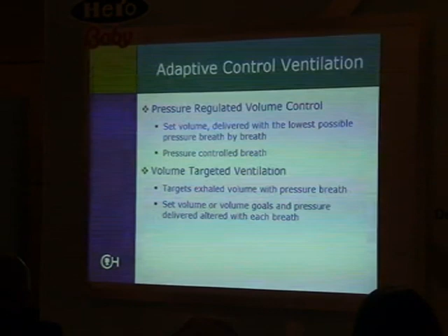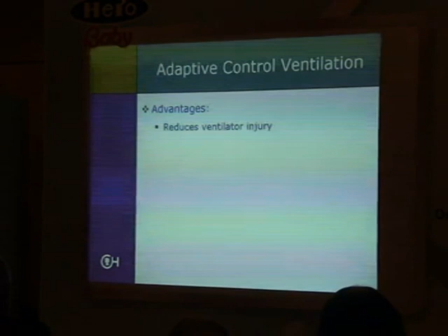Some of the advantages with this, there's the reduced amount of lung injury because you're setting that targeted tidal volume instead of the targeted pressure, so you know that you're maintaining a consistent tidal volume every time, but you're getting the benefits of the lower amount of pressure each time. So for those who believe that pressure is still the injury, for those who believe that volume still causes the injury, these modes give you the best of both worlds because you're getting to set your pressure, your volume, ensuring that you get consistent ventilation, as well as getting the lowest amount of pressure possible for each breath.